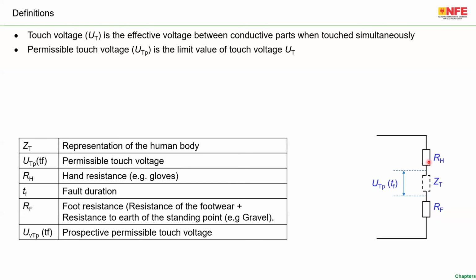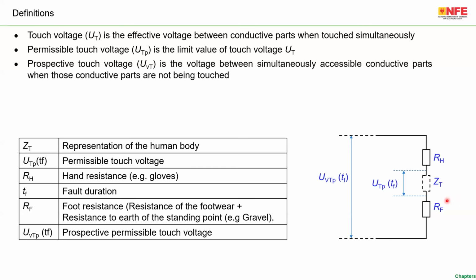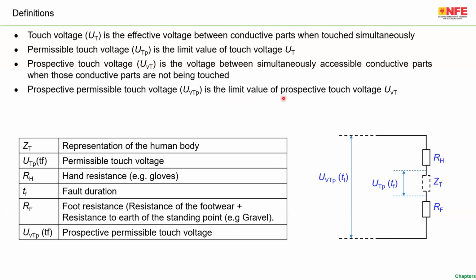Now, in a typical situation in a large substation, skilled people are supposed to go with proper PPEs. Under such conditions, there is one more parameter called prospective permissible touch voltage. The definition of prospective permissible touch voltage is the limit value of prospective touch voltage UVT. So touch voltage is the effective voltage between conductive parts when touched simultaneously. Permissible touch voltage is the limit value of touch voltage, that means what maximum you can allow. The first one is the actual voltage. The second one is what maximum is allowed. Prospective touch voltage is the voltage between simultaneously accessible conductive parts when those conductive parts are not being touched. Prospective permissible touch voltage is the limit of prospective touch voltage, UVT.